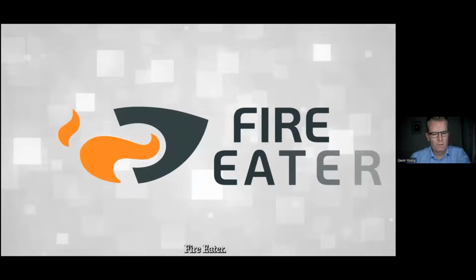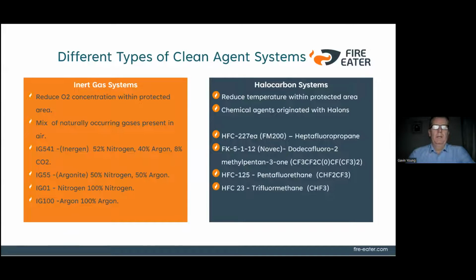Okay. So there are two different camps, or two different types of fire suppression system. There are the inert gas systems, and they operate by reducing the O2 level within a protected area, thereby taking off one of the elements. Basically, fire cannot sustain itself once you bring down the level of O2. It's a mix of natural gases that occur in the atmosphere.